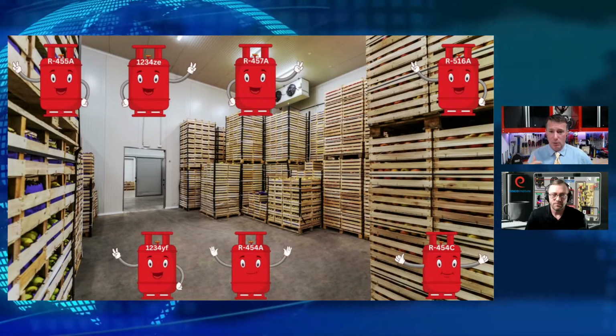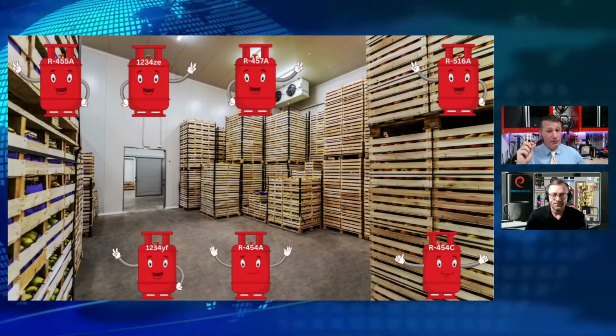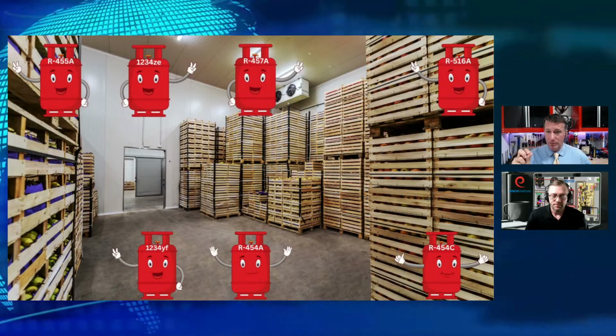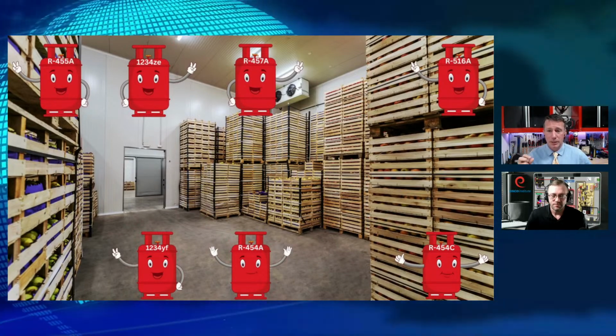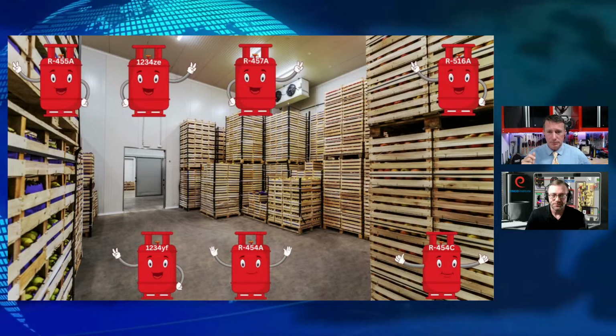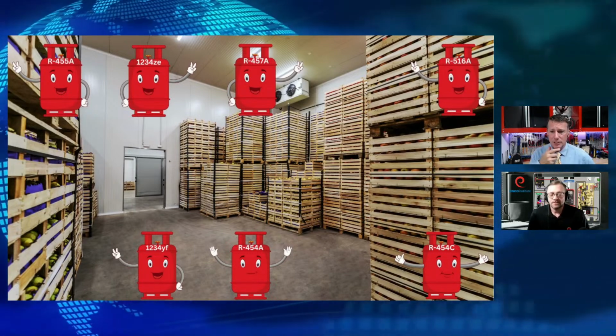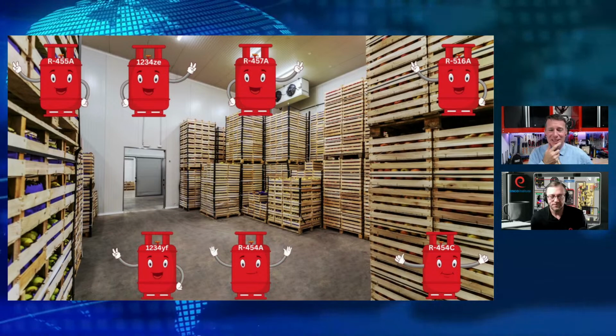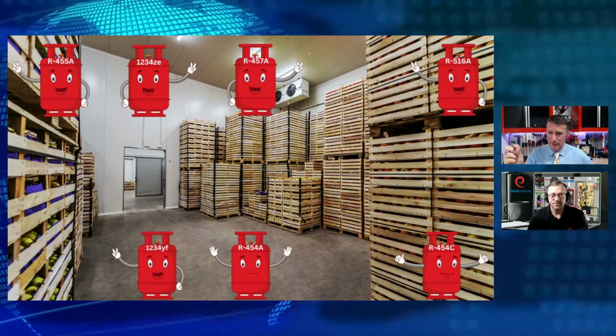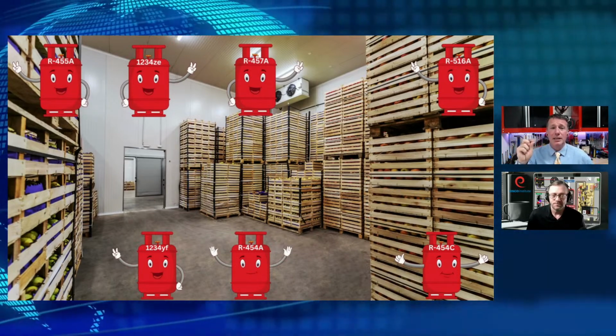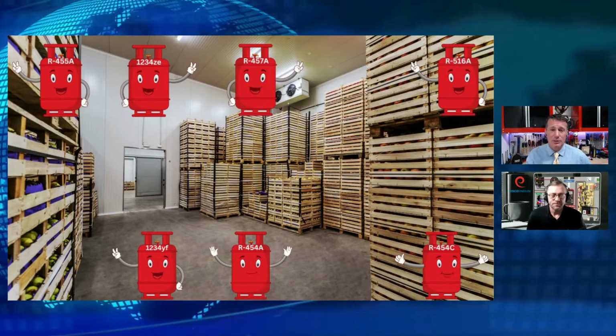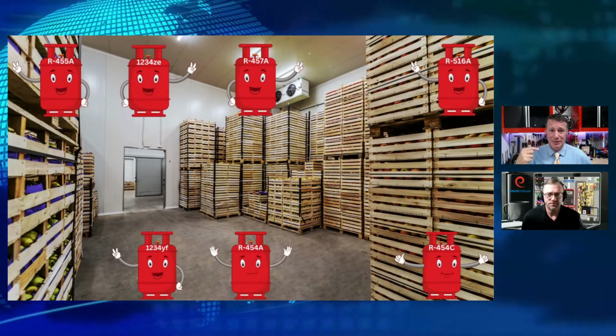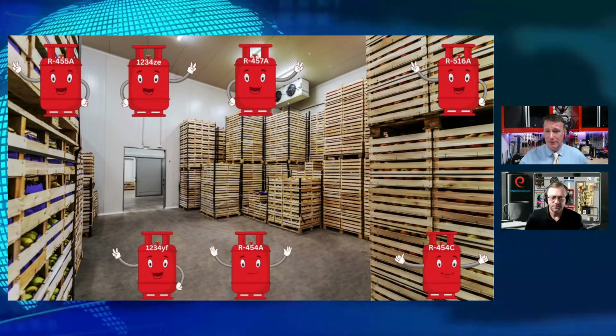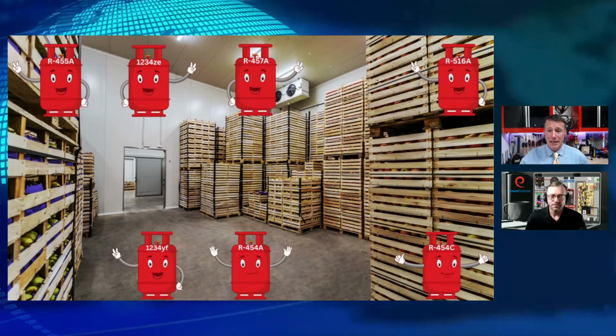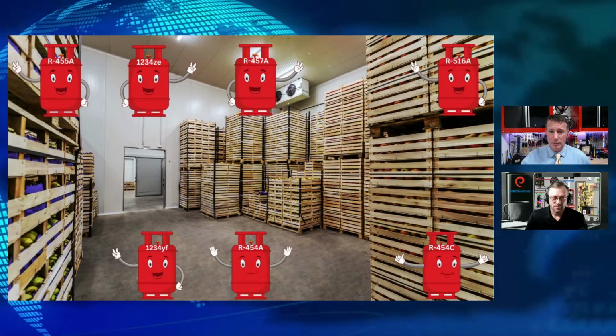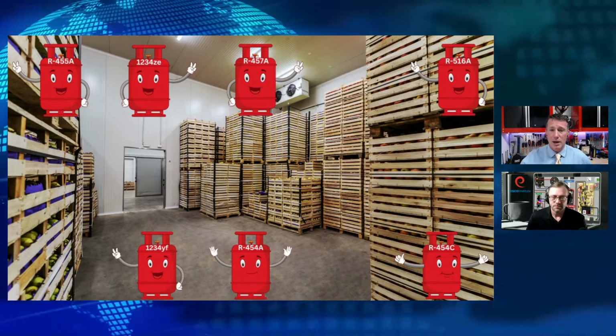We're going to see 1234YF. We're going to see 454A. We're not going to see B. Remember that B is another medium temperature, medium pressure application. So we are going to see 454A and 454C utilized in this process, though. And we've got our 1234ZE, which means now we've got some additional blends in there with that 455 and our 457 and 516. So very common refrigerants that we will see in new equipment for our cold storage warehouse.